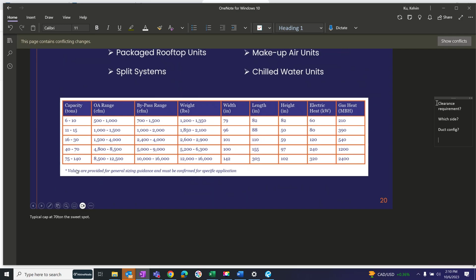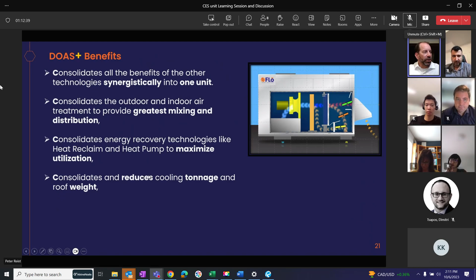We consolidate other technologies like heat reclaim and heat pump technologies. The more you can bring these into single units - I'm not saying you only want one unit in a store - but the more you consolidate your units into fewer, the more you can take advantage of these technologies. If you have a lot of units that each have tiny little bits of airflow, you really can't take advantage of heat reclaim and things like this, and you're spending a lot of money. So this consolidates and reduces the tonnage, cooling load, and roof weight.